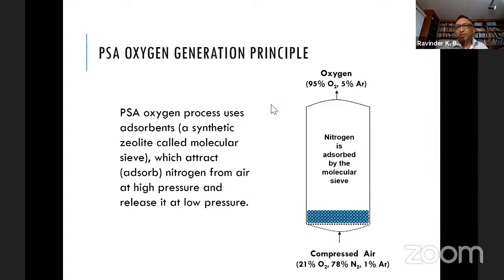And that is a big limitation: the oxygen produced by a PSA is a maximum of 95.4% pure. Now, this can be purified by using a secondary purification system, but that's never a practical thing. It's not economical. It is quite expensive to do that. So the main limitation for PSA oxygen is that 95% purity is the maximum you can achieve. There are certain applications where you need more purity than that, but medical is certainly not one. In medical use, anything above 90% is good enough.